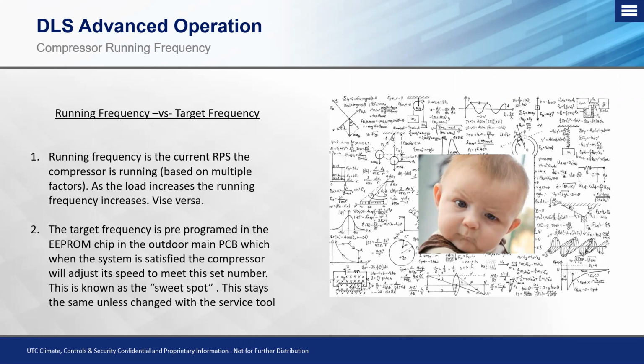Now looking at the target frequency, this is the pre-programmed value in the EEPROM, or the main chip of the board. That main chip of the board, or the EEPROM chip, is the brains of the operation where this algorithm or set of rules is stored. Essentially, as the sensors report information back to the board, this is the part of that board that receives that information and makes a decision based off of what information is sent to it, so that it can control various parts of the outdoor unit and also communicate with the indoor unit. Okay, so that EEPROM chip is going to be on that outdoor main control board.